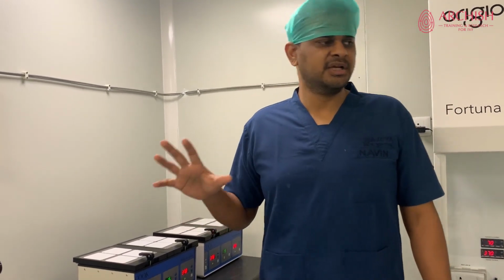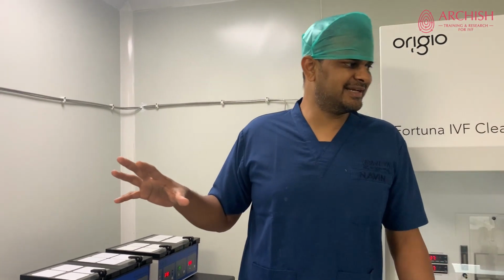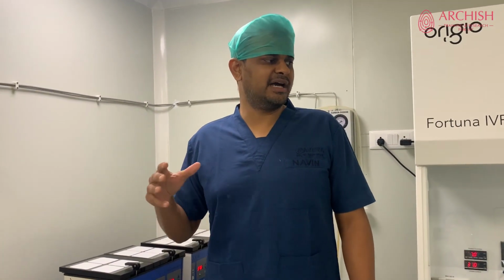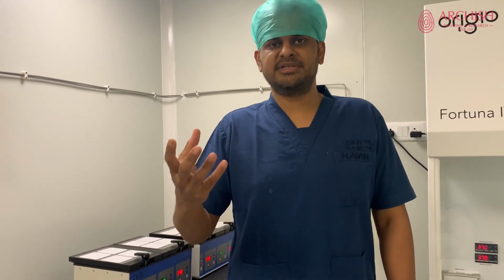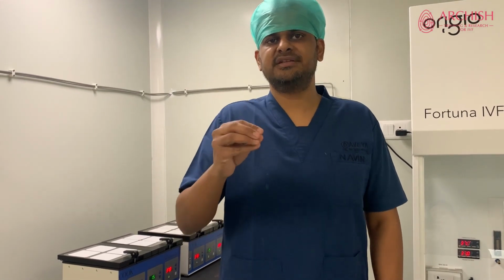But these are pretty much the most important parameters inside the lab, which are at a higher degree or at a CO2 level. Now something cold that you need to also check inside an IVF laboratory, which is not at 37 degrees, is your refrigerator, in which you store the important media and other consumables like oil, which are going to be used for preparation of your cycles. It's important that this fridge temperature also ranges between 4 to 6 degrees.